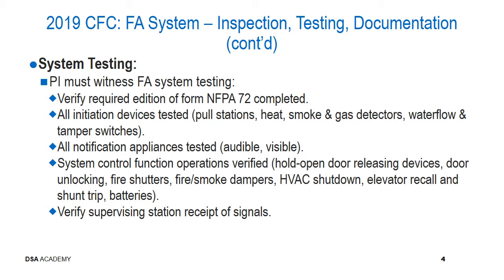System control functions, that these operations are verified, such as door hold opens release upon fire alarm, that the door unlocking or fire shutters or fire smoke dampers operate correctly, that the HVAC system shuts down, and that elevator recall and shunt trip operates properly. Verify supervising station receives all signals. Ask the contractor to provide a copy of the printout from the supervising station.